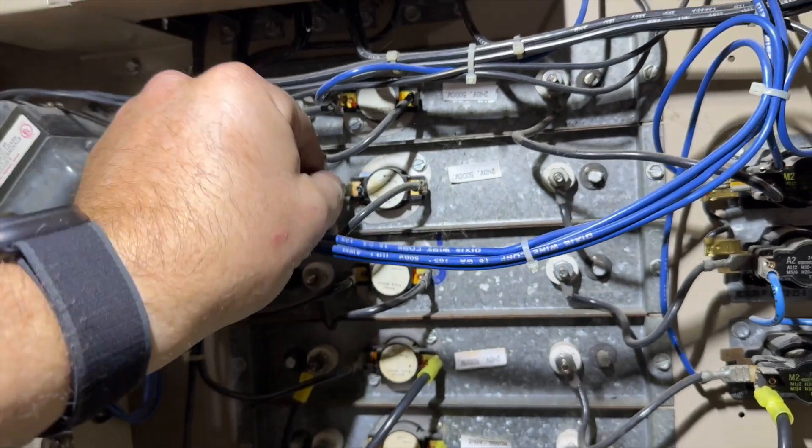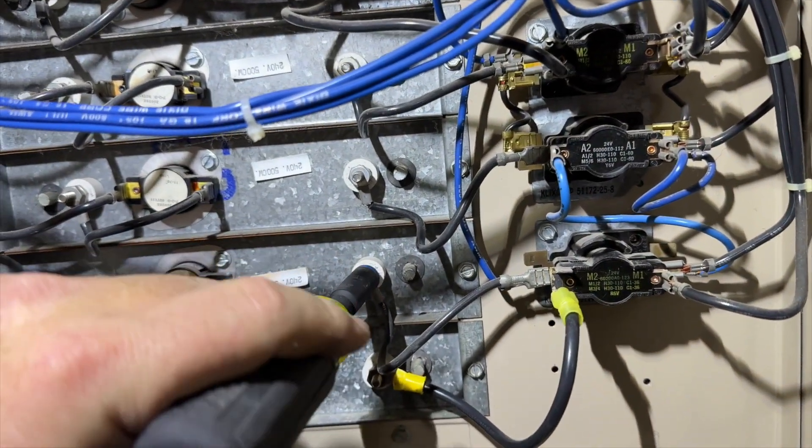I'm gonna just make sure all this other stuff is tight, because usually when you got loose stuff, that's when you get melted wires. These are three-eighths, so we can use that to tighten them up if you have aluminum on.